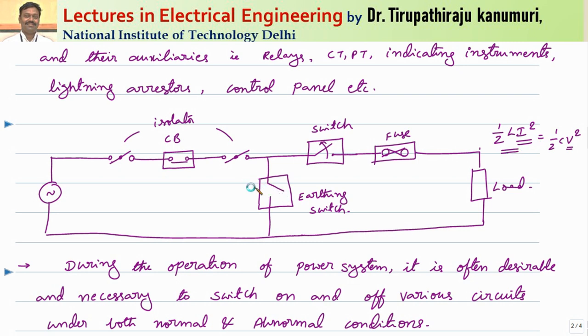In the case of a transmission line, whenever the circuit breakers are disconnected on both sides, then the earthing switch will be connected, so that all the charge will be discharged to ground, and then only you do the repairing. Sometimes when some problem comes in your home — such as for a fan or inductive circuits — you can observe that the person who comes for checking it will first short circuit the terminals or connect the terminals to ground, so that whatever charge is stored will be discharged to ground, and then only he will touch and operate your equipment. The reason is the energy storage elements.